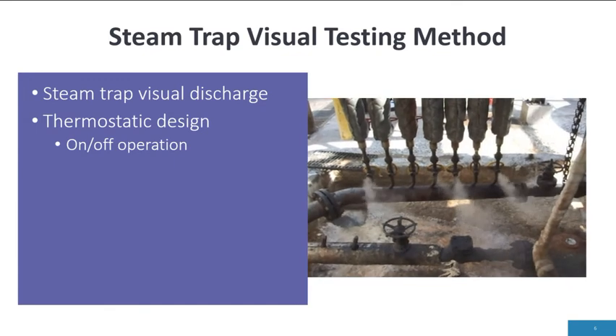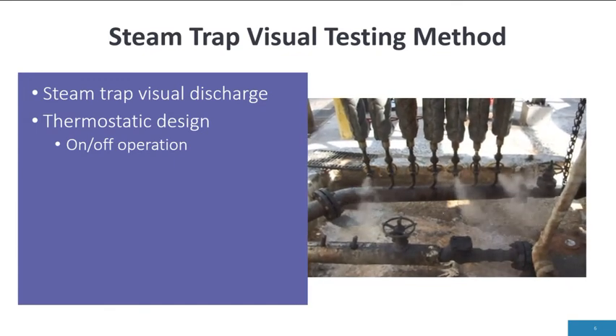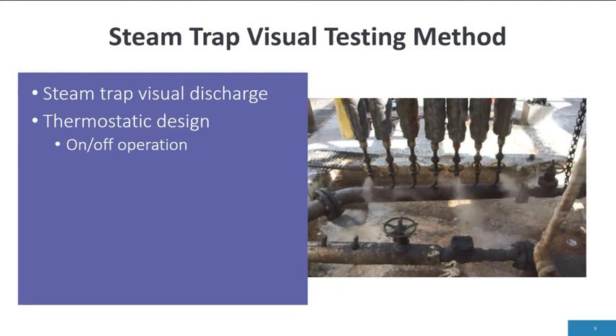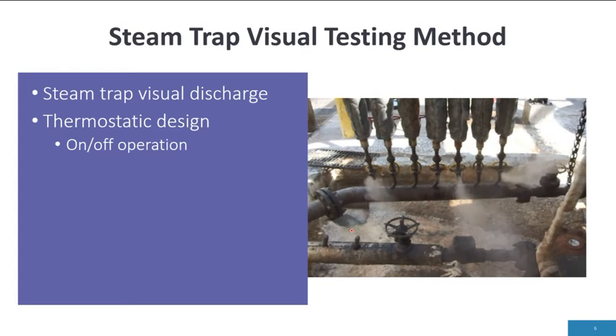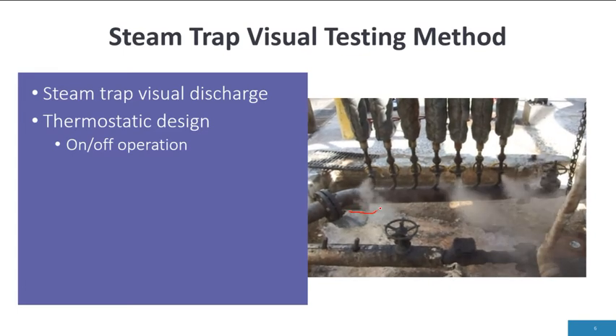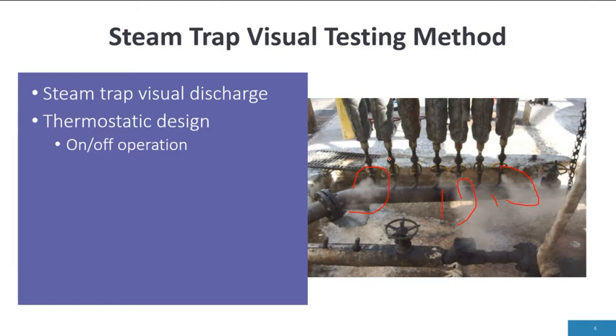In another application, the steam trap is blowing, leaking, blowing, leaking, blowing. These are thermostatic design steam traps, which have a distinct on-off operation. We should see a discharge and then a shutoff. When we open to atmosphere, we can tell that they are blowing or leaking.